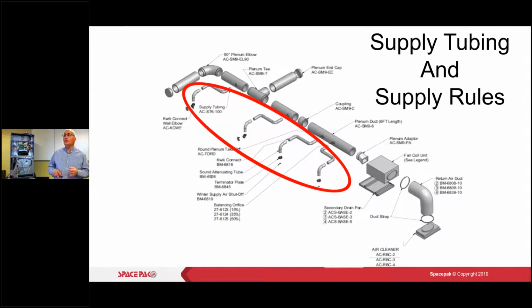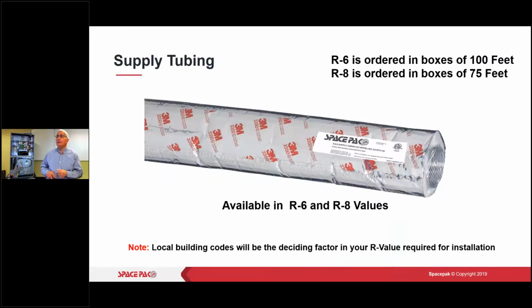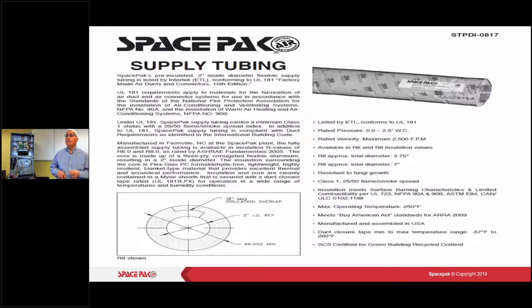All right, so our rules here when it comes to our tubing: there's our tubing in R6 and R8 and the length of what comes in the box. Local code's going to decide whatever you guys need when it comes to R-value. You're going to use that tubing. You're going to slide it through your attic space. You're going to slide it down the walls. We want to try to grab closets and corners so we can go from attic through second floor to get down to first floor. So try to find closets that allow you that path down to the first floor.